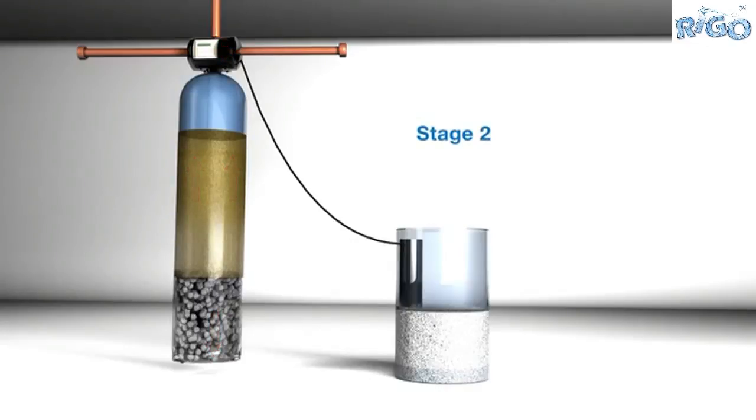The second stage requires us to pull the brine from the tank. When this stage begins, water enters the system from the left. Take close attention to the arrows here as there are two things happening simultaneously. Water is diverted down through the freeboard, back up through the dip tube, and out the drain. As the water passes the top of the fill tube, a siphon is created. This siphon draws the brine from the tank.